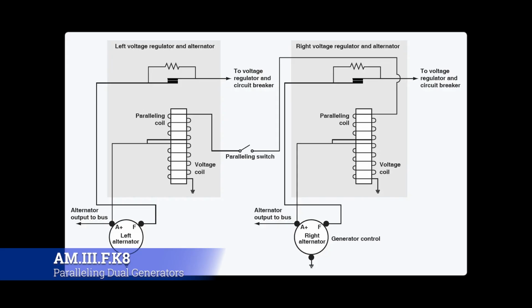It does this through load sharing, so the generators have to share the load proportionally based on their rating. If one's rated higher, it takes more of the load; if one's rated lower, it takes less of the load. This is achieved through a governor control for frequency or active power and a voltage regulator adjustment.